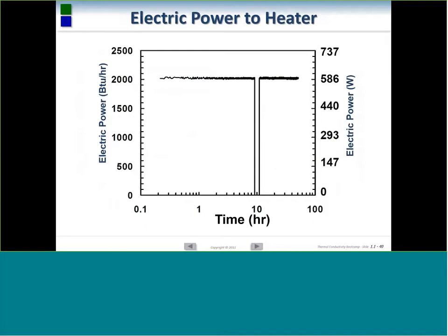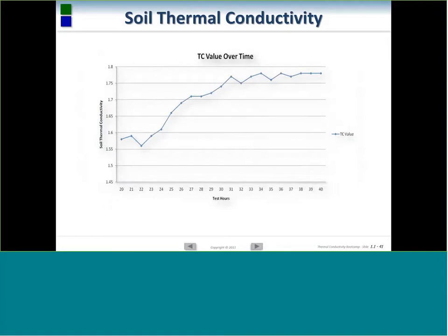Kind of interesting take. And then the other question people ask, well, how long do we need to run a thermal conductivity test? The nice thing about the GLD software is you can alter the amount of time that you're going to run your test for. So you can truncate and run your test from 12 to 20, 21, 22, 23, up to 40 hours.